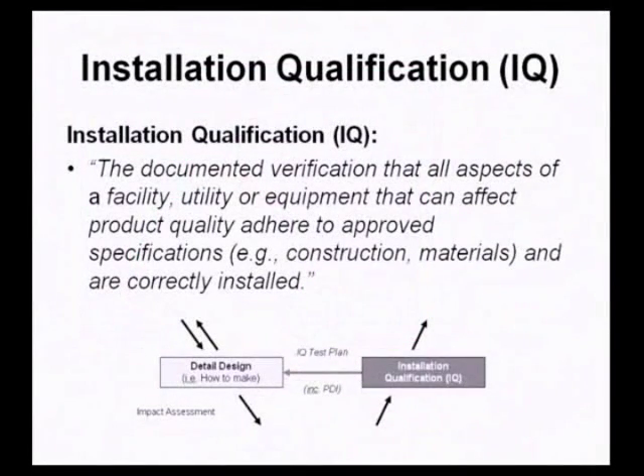Installation is the documented verification that all aspects of a facility, utility, or equipment that can affect product quality adhere to approved specifications and are correctly installed. From the V-Model, our IQ is based on our detail design documentation, and the verification is twofold: we want to make sure all critical components are of the correct specification in the context of construction documentation, materials of construction, calibration, etc., and secondly, that they are correctly installed.